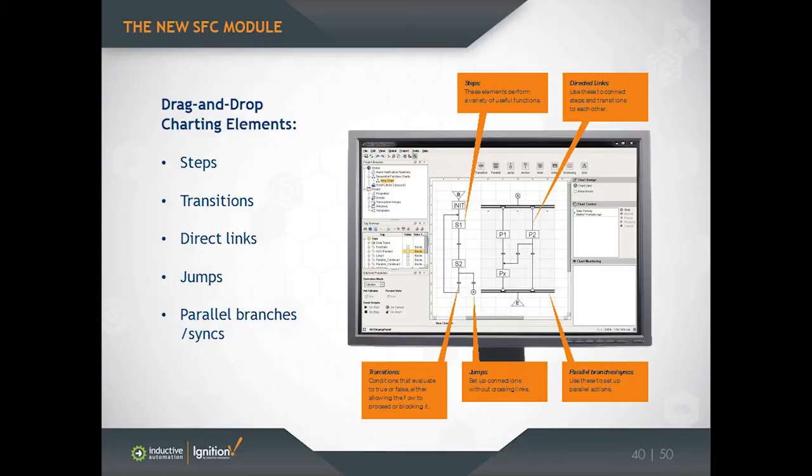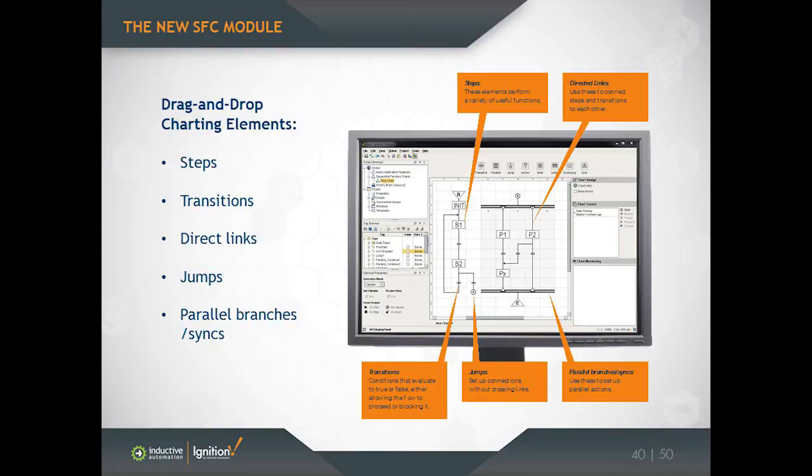There's a variety of other elements like jumps that I'll show you in a little bit. But the other important element to talk about here is the parallel branches and syncs. So those fat horizontal bars there, that designates a parallel section. And what that does is it lets multiple branches of logic execute simultaneously. And this is really one of the most important parts of what makes the SFC language so powerful, is that it makes writing concurrent logic really easy.